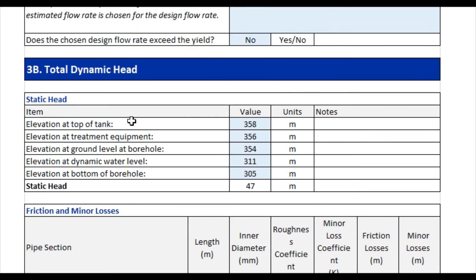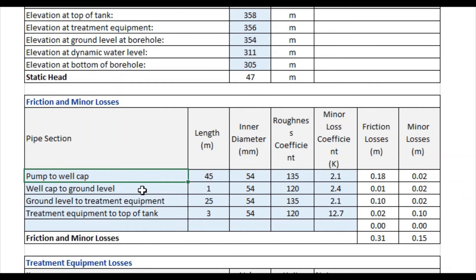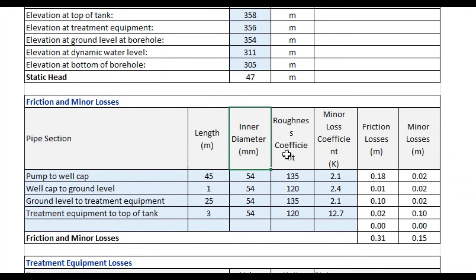Next, we'll look at total dynamic head. The first part is to enter elevations from the top of tank all the way down to the bottom of the borehole and various points in between. The spreadsheet automatically calculates static head — the difference between the top of tank elevation and the dynamic water level elevation. Next, the spreadsheet automatically calculates friction and minor losses based on information we enter about our system. There are sections from pump to well cap, well cap to ground level, ground level to treatment equipment, and treatment equipment to top of tank. For each section, you can enter pipe lengths, inner diameters, roughness coefficients, and minor loss coefficients.